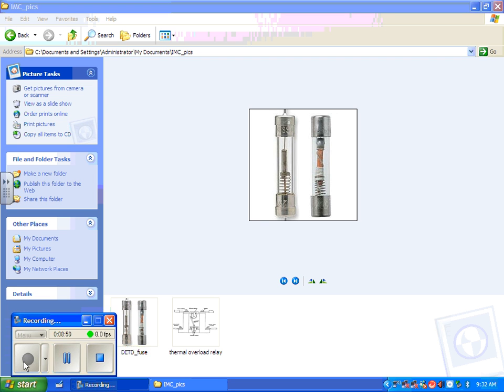Our book talks about dashpot overload relays. And dashpot overload relays are sometimes used for starting a motor to allow the inrush current to happen before some other heat sensing device kicks in. Also, they can be used as just a timing device, because they're just creating a time delay from when it started to when the contacts are closed.